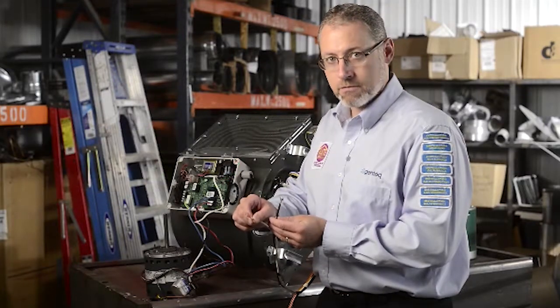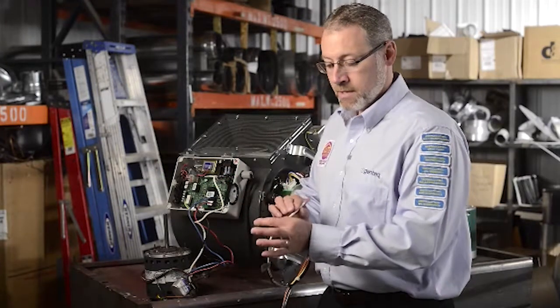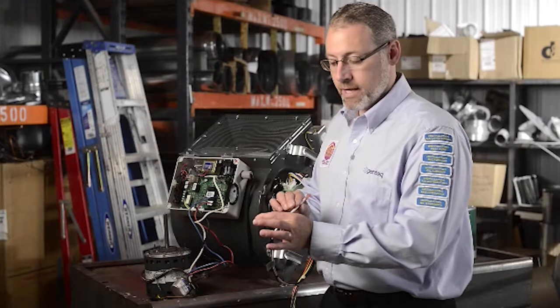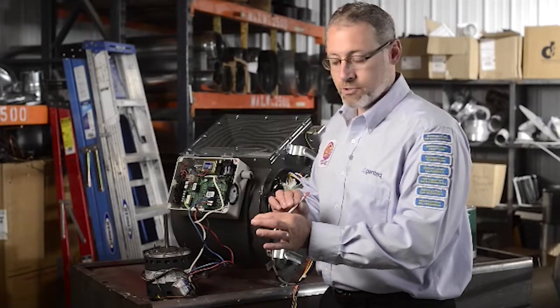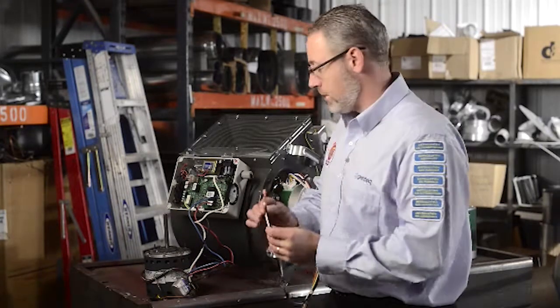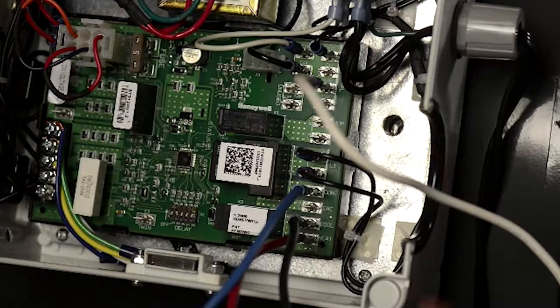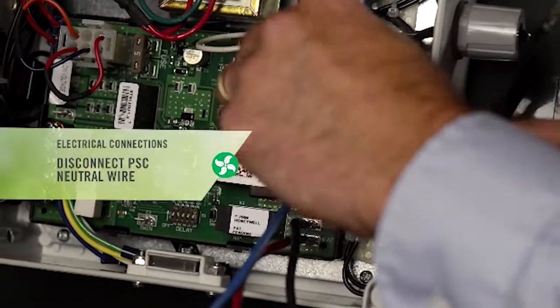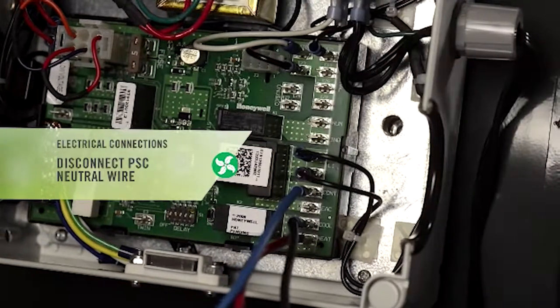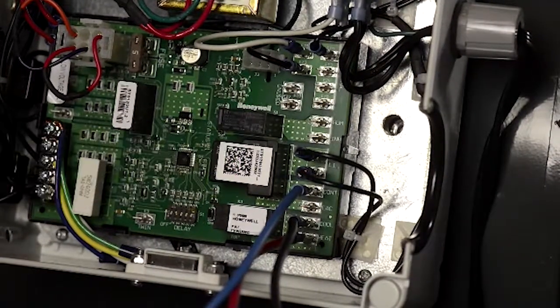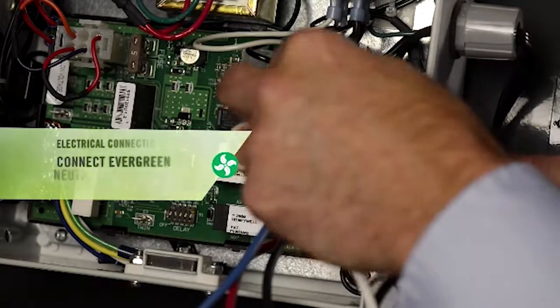And you'll notice that the white wire already has a female 1/4 inch spade terminal on it, and the black L1 wire already has a 1/4 inch spade terminal on it with a male piggyback. So here we have our PSC motor connected to the board. We're going to disconnect the neutral wire from the PSC motor to the board, and we're going to take the neutral wire from the Evergreen IM harness and put it right back on the same terminal.